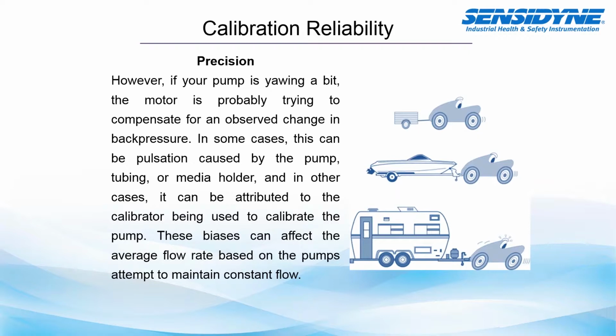In some cases, this can be pulsation caused by the pump. It can be caused by tubing or the media holder. If you're using a cyclone or another type of media holder, this could also contribute to it. In other cases, it can be attributed to the calibrator being used to calibrate the pump. Now, these biases can affect the average flow rate based on the pump's attempt to maintain constant flow. So if your pump is trying to constantly change, you're not really seeing a stable result in your calibration readings.